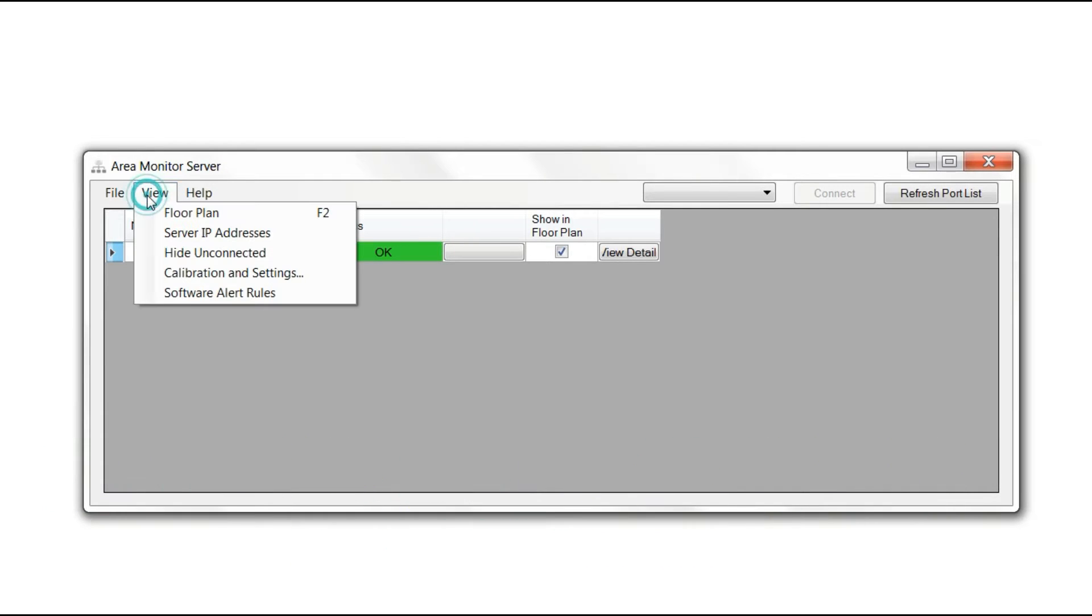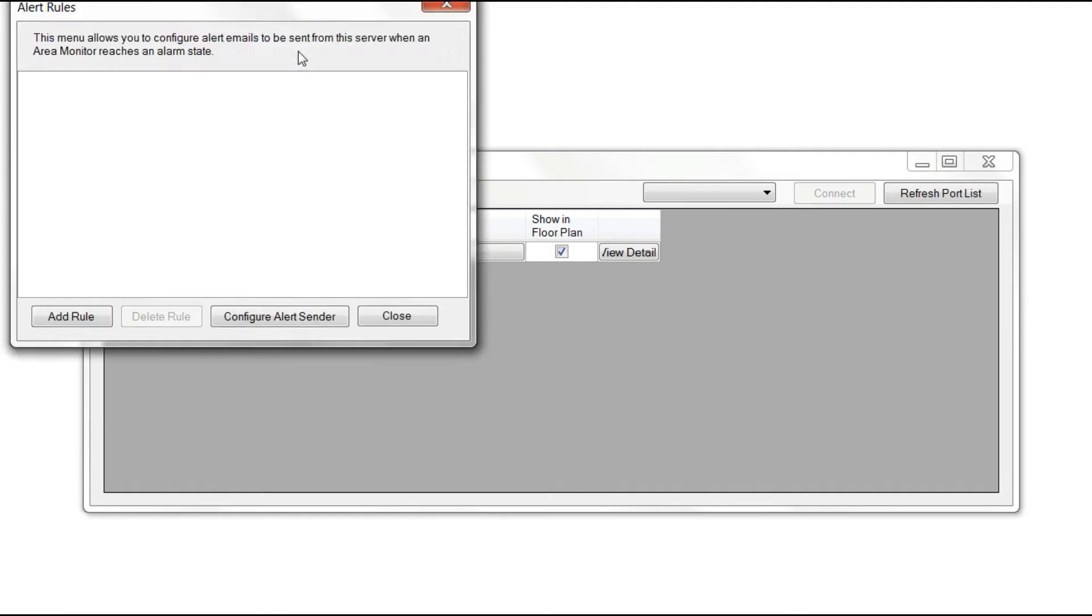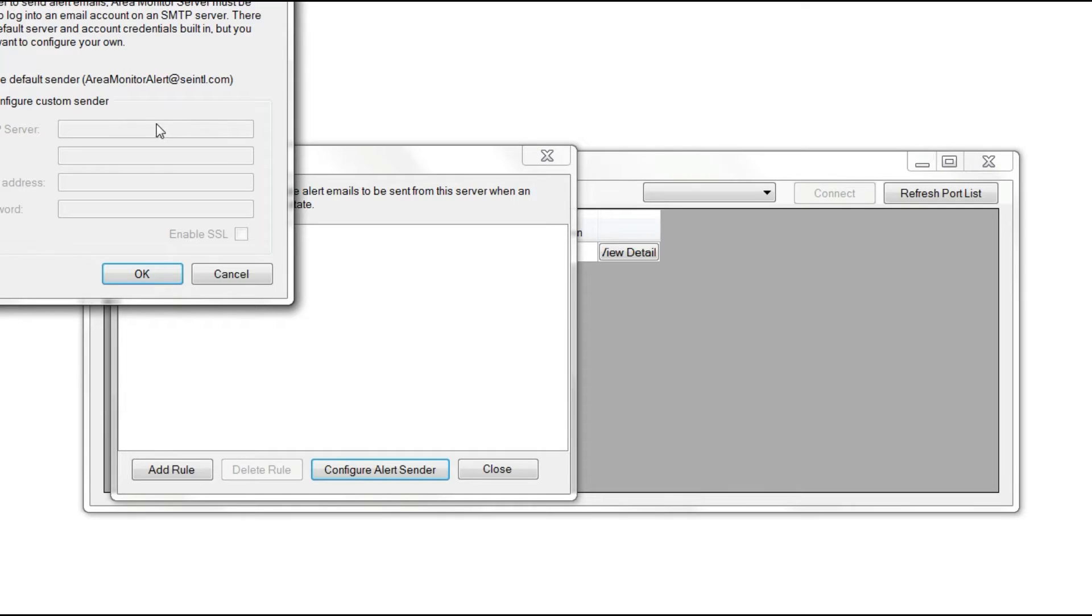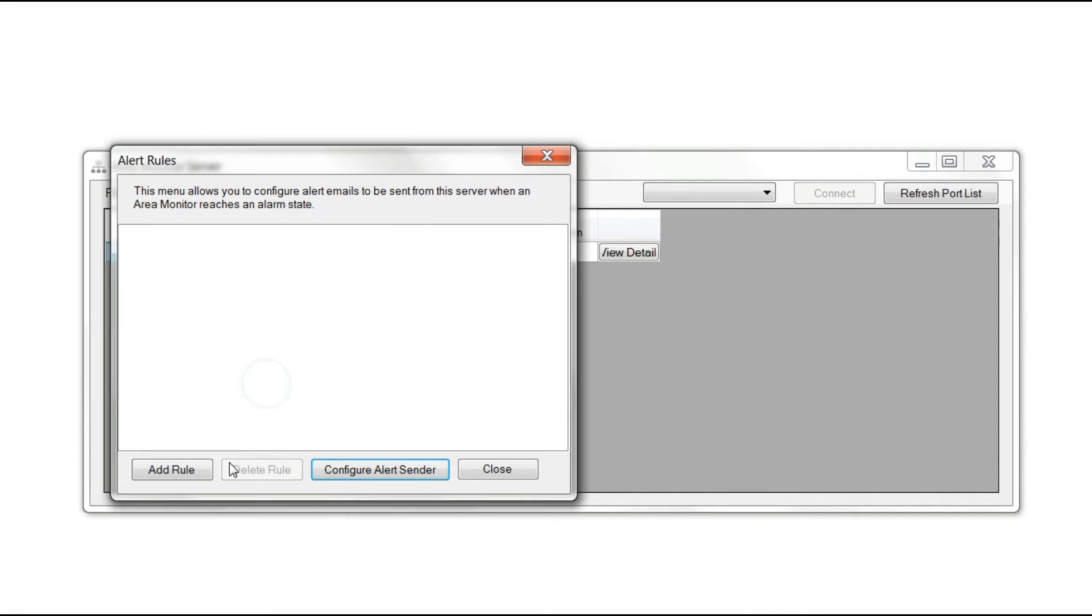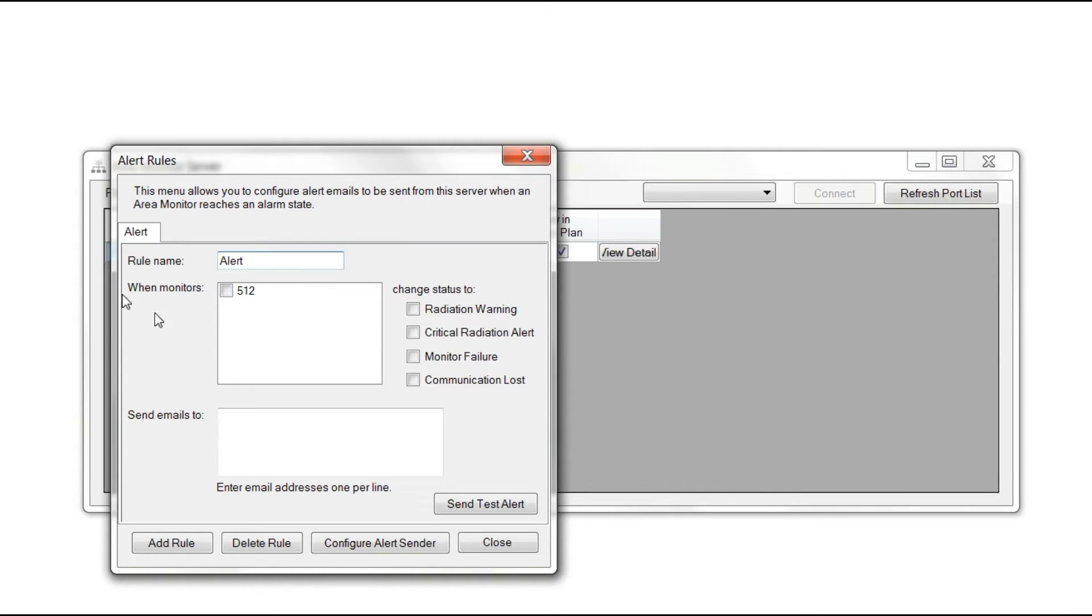Located in the View menu, you can set up different alerts to be sent to different locations from the software. To configure an alert, press Configure Alert Sender. By default, you have SE International's mail servers to use. To add a rule, click Add Rule, give it the title you want, and select the area monitors you're connected to that you want the alert sent from.